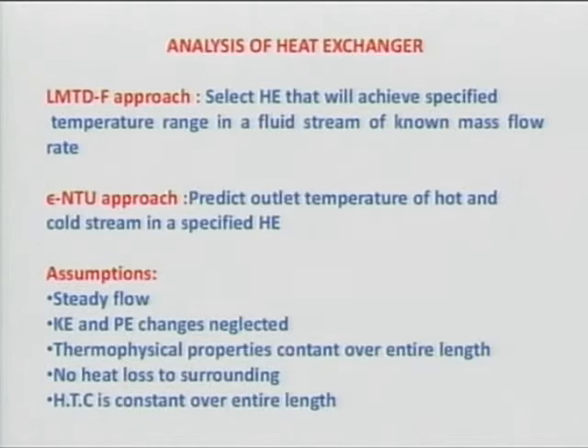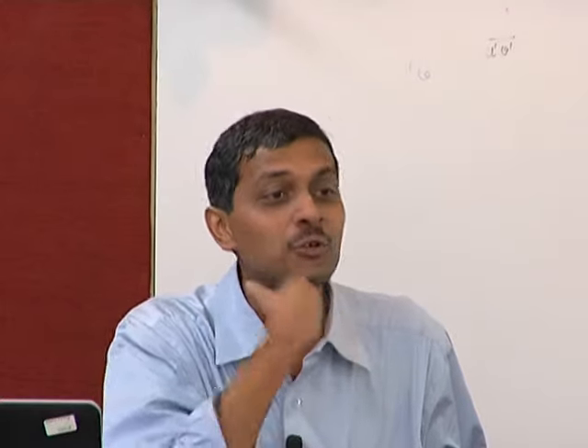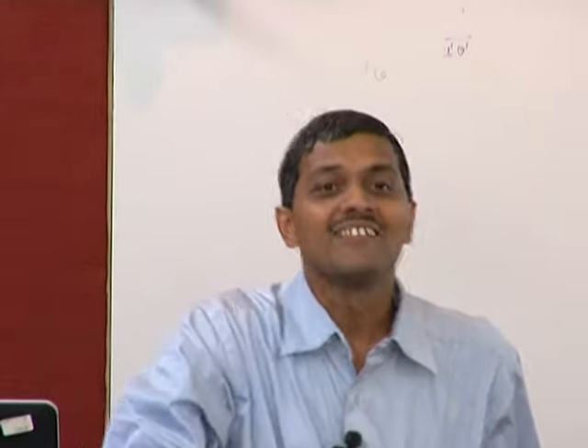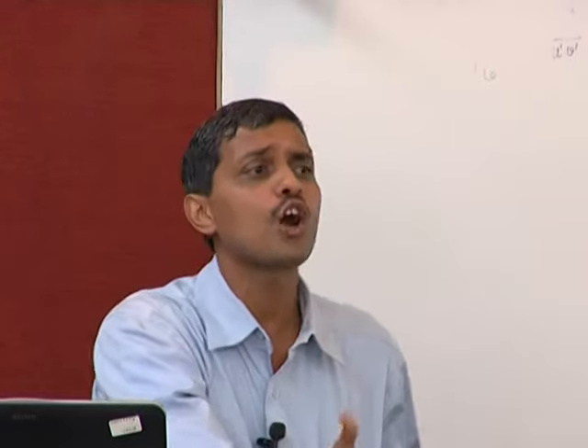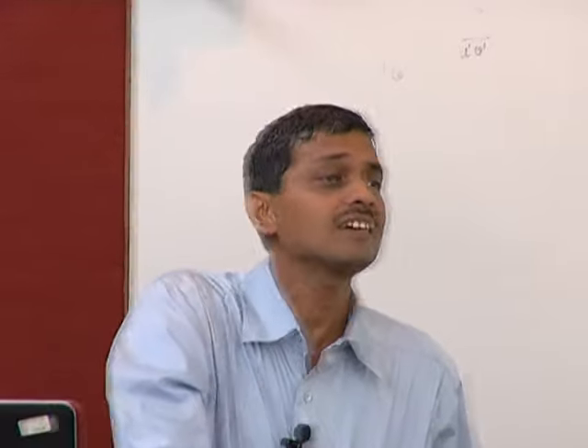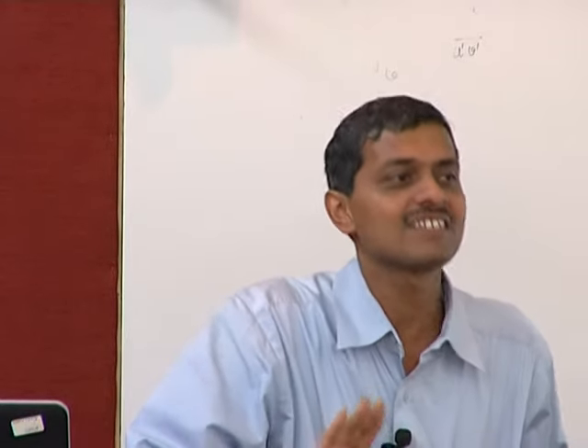For varying properties, in the correlations there is a term (μ_b/μ_wall)^n that accounts for property variation. Thermophysical properties being constant is an assumption — perhaps not unreasonable for a plate-fin exchanger with air as the fluid. No heat loss to the surroundings: there is bound to be heat loss; the exchanger is not outside the world. Heat transfer coefficient constant over the length: this is not such a serious assumption because heat exchangers are quite lengthy.